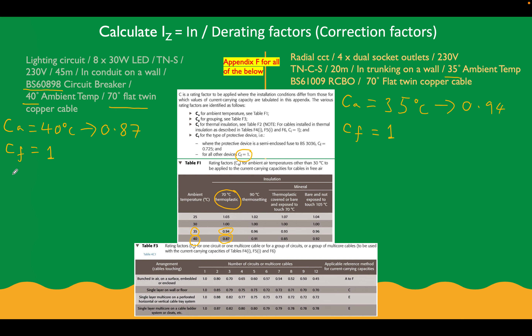Let's calculate IZ for the lighting circuit. IZ equals our IN of 6 amps divided by our correction factors multiplied together: 0.87 × 1. That gives us 6.89 amps, which we round to 7 amps. So our IZ for the lighting circuit is 7 amps.